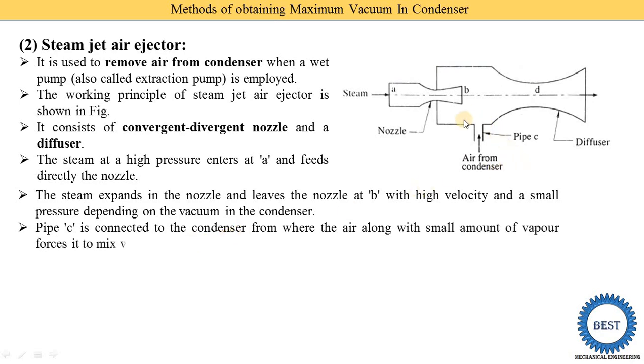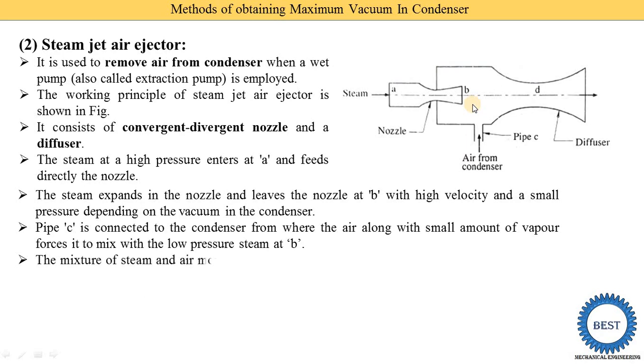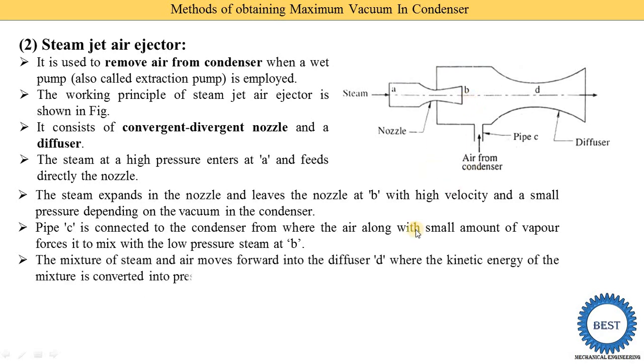Pipe C is connected to the condenser, from where the air along with a small amount of vapor is forced to mix with the low-pressure steam at point B. Then this mixture of steam and air moves forward into the diffuser. In the diffuser, the kinetic energy of the mixture is converted into pressure energy — kinetic energy is reduced and pressure energy is increased — and then the mixture of steam and air leaves the diffuser.